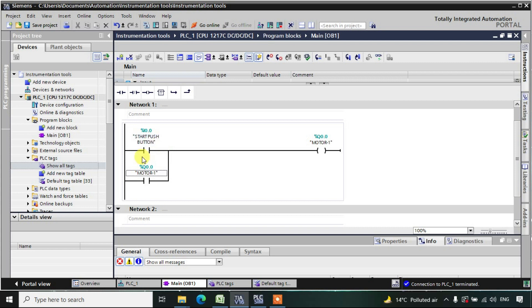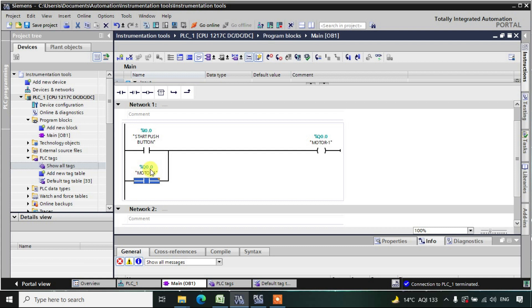Let us see what is going on. When you press this start push button, the motor will be in the high state. Now because the motor is in the high state, the address Q0.0 is transitioning from 0 to 1 — it is high. Because this address Q0.0 is high, this NO contact will also turn into NC, so power is also supplied from this parallel branch. Now even if you release the start push button, the output will remain in the high state because this NO contact will continuously supply power to the motor.